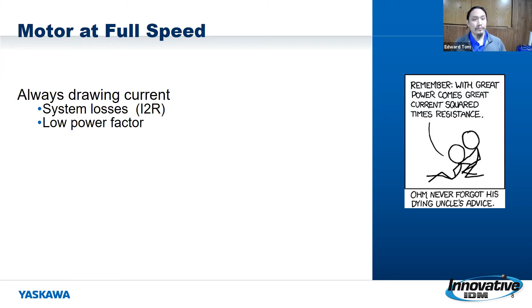You're going to experience some of those losses, something to be taken into account. The other is low power factor. I'll get into a little more about power factor later on, but ultimately power factor can be looked at as how efficiently we are using the power that's being supplied to us. A motor running across the line is going to result in a lower power factor depending on the load that's being put on there.